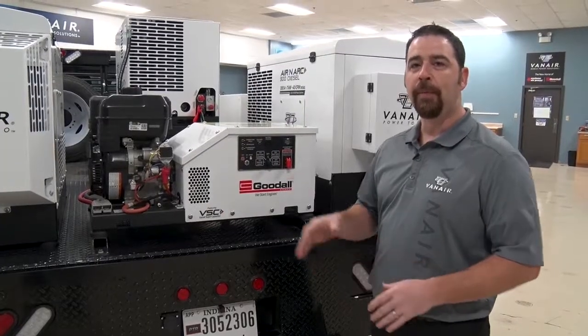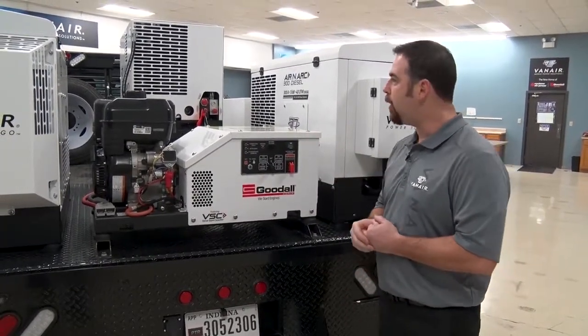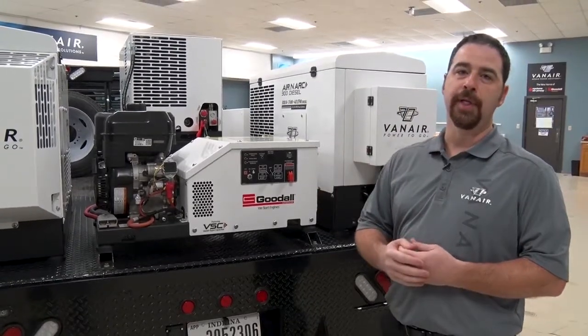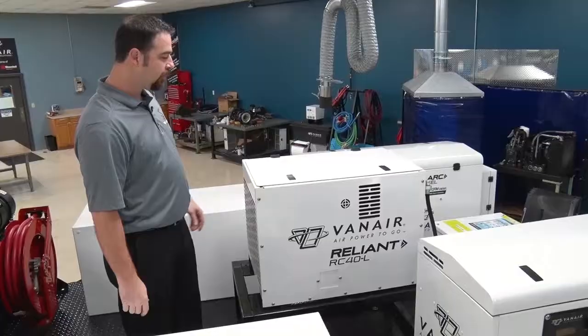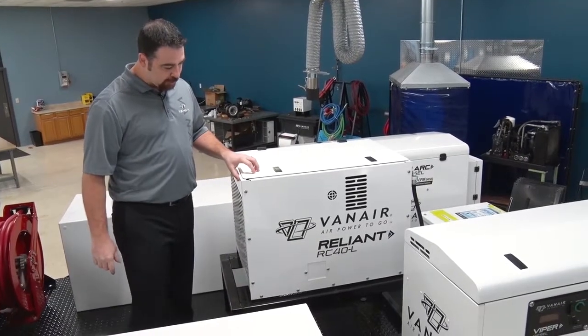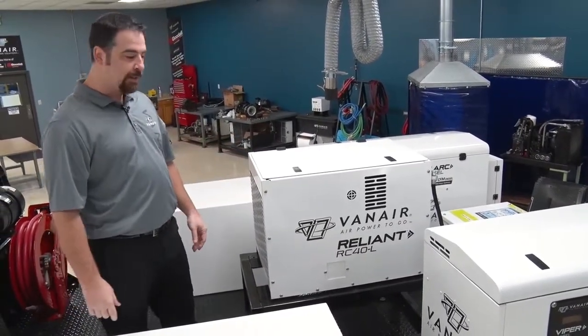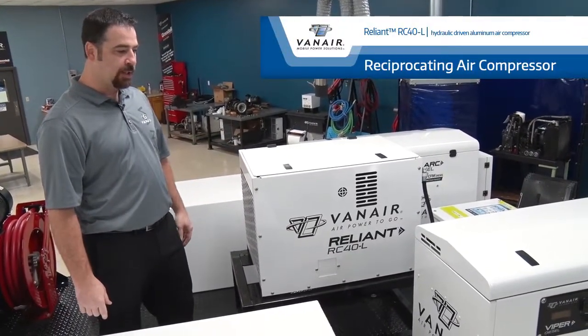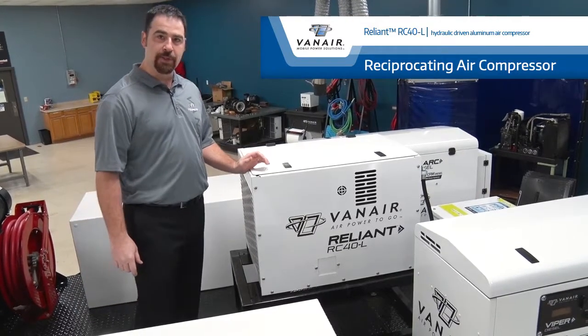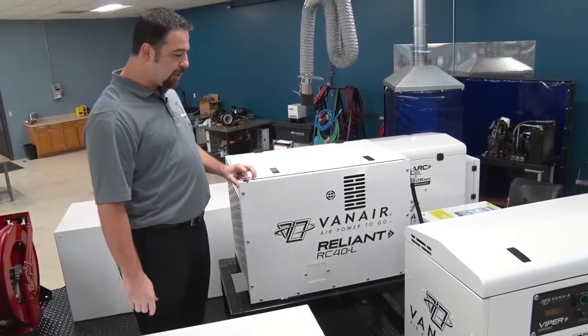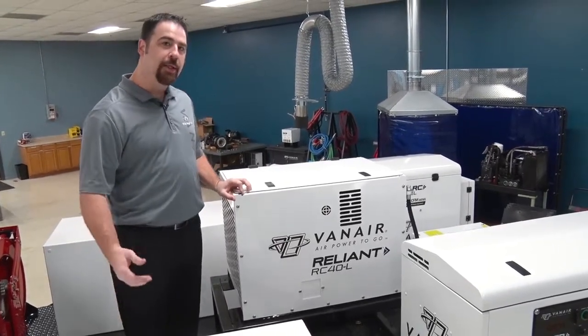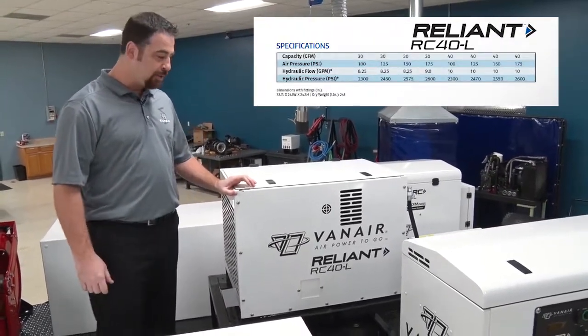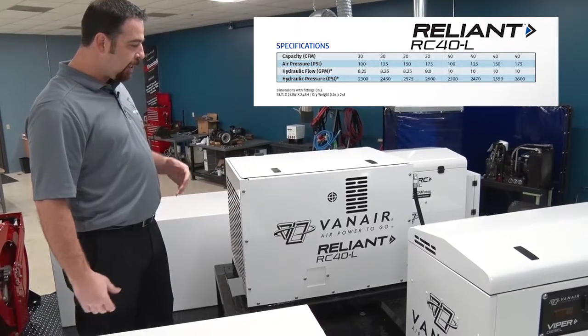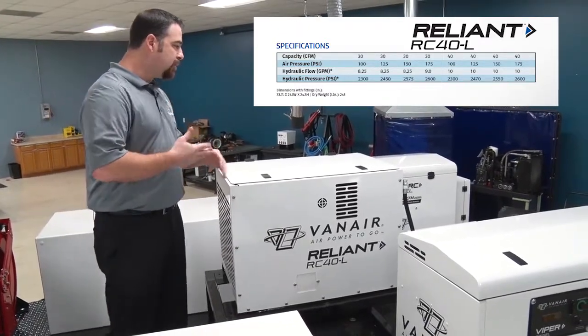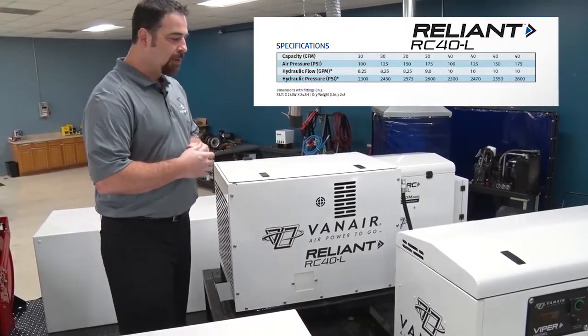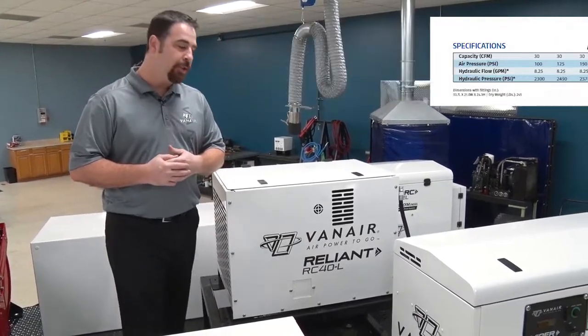Now we'll move up on top deck of the truck and talk about our RC40 reciprocating compressor. Up top here on our demo truck, we have our RC40 Light, one of our newer offerings in our reciprocating hydraulic driven compressor line. This is a 2-stage compressor, running 175 PSI output, in a lightweight package just over 200 pounds, giving us 40 CFM of true air output.